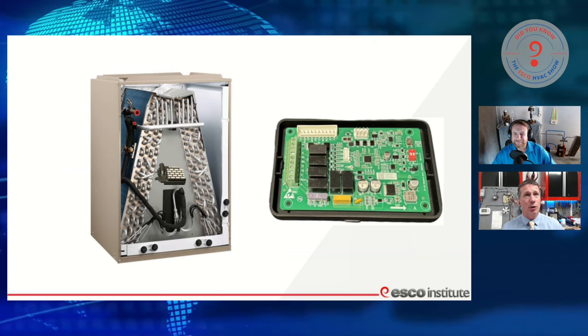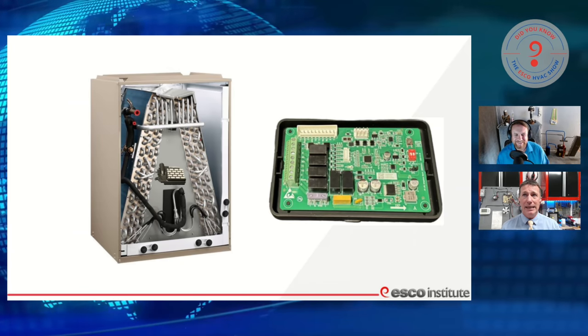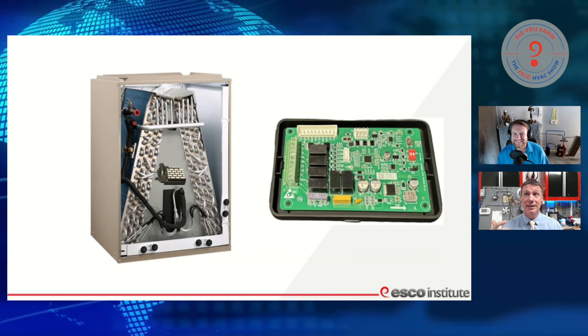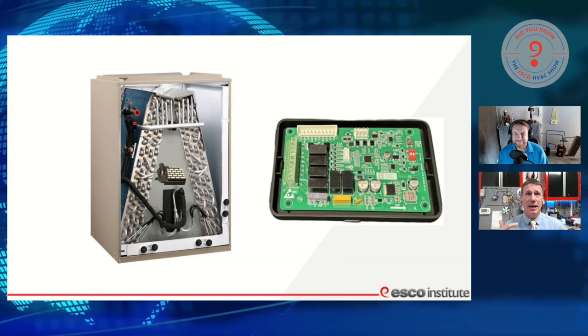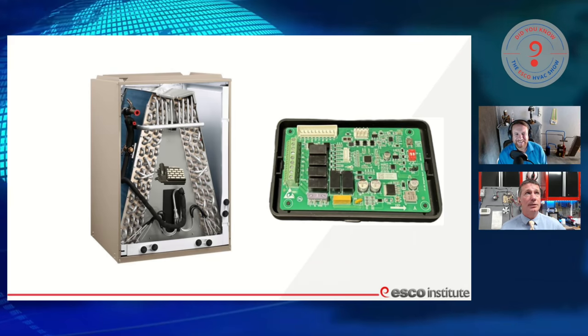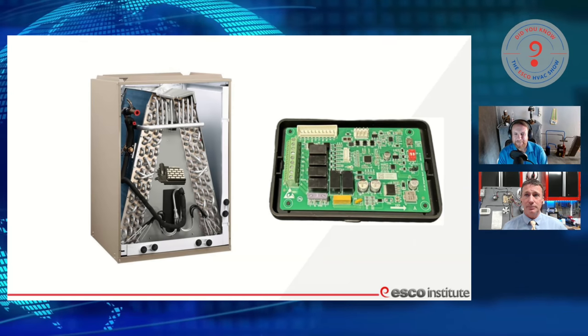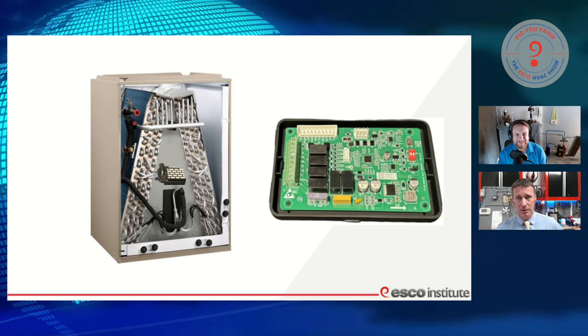If we think about the coil, the coil is not going to be rated any differently for R32, R410A, or R454B — they're all operating on very similar pressures. We might possibly have a change of components if there's a potential place for leaks that a manufacturer recognizes, but there aren't any I've seen. So we can use the same design of coil, and if it is going to be used on an A2L refrigerant, I just need to add a sensor to it. We will be able to put new systems on existing gas furnaces — I'm waiting to see that specification from the manufacturer, but in my mind, I'm adding a control to a refrigeration system.